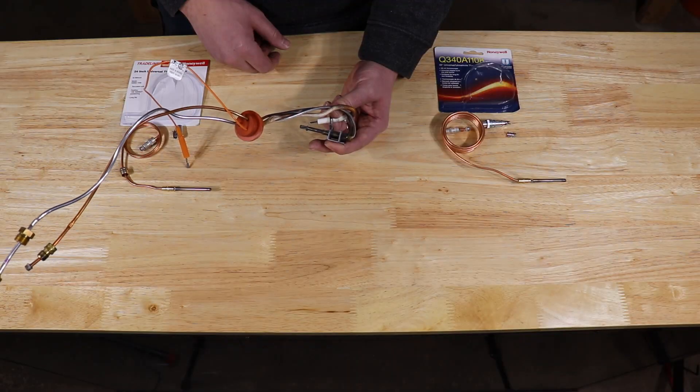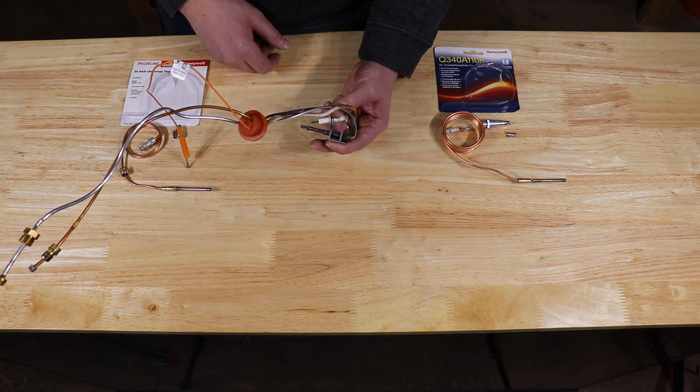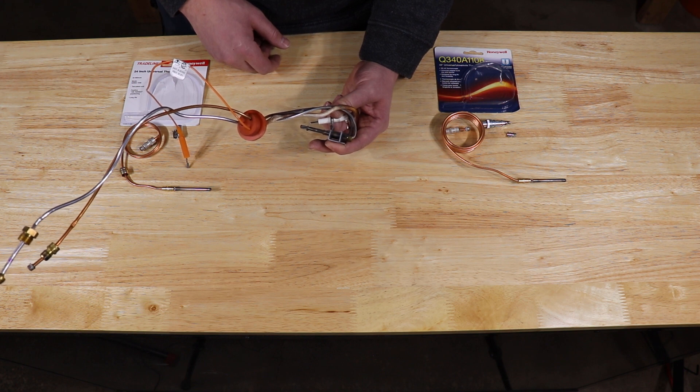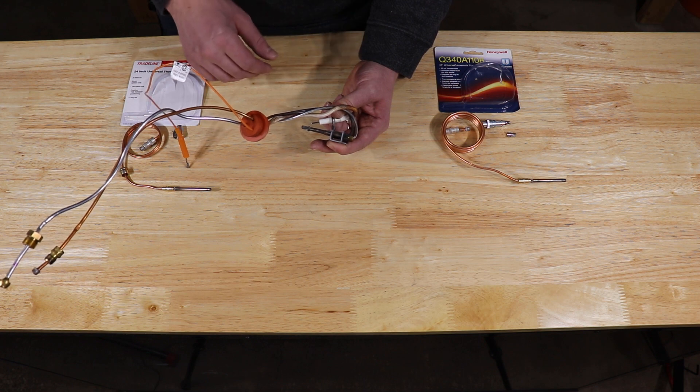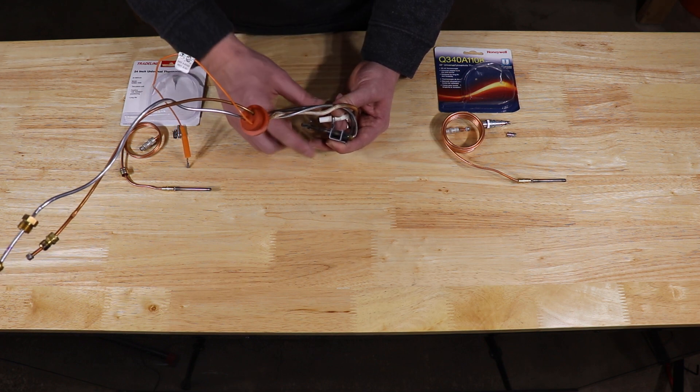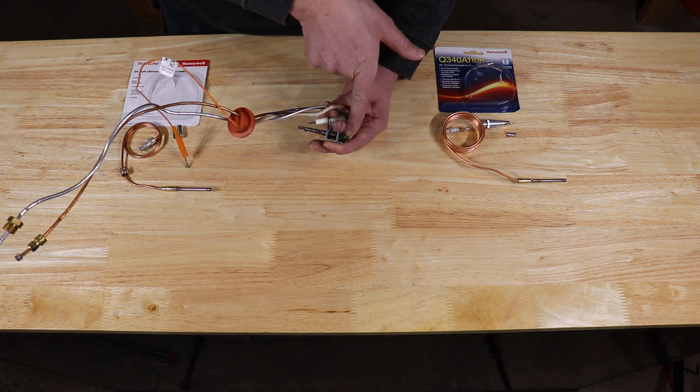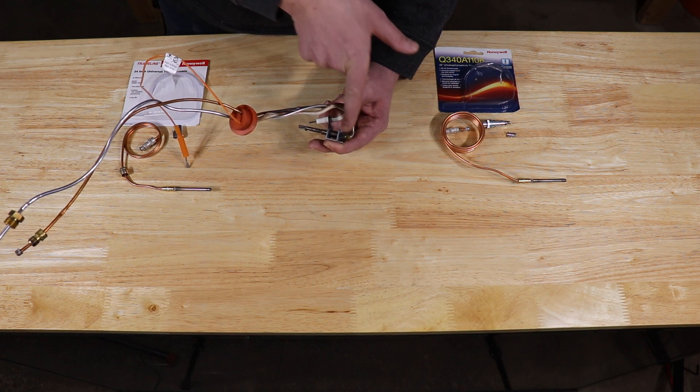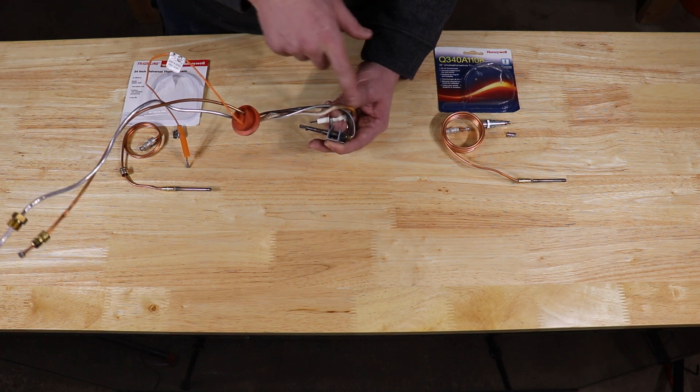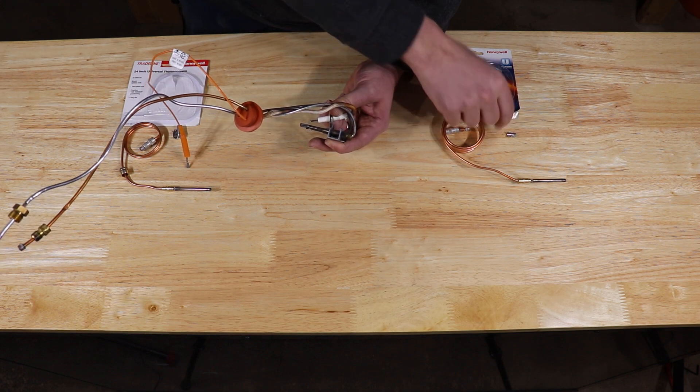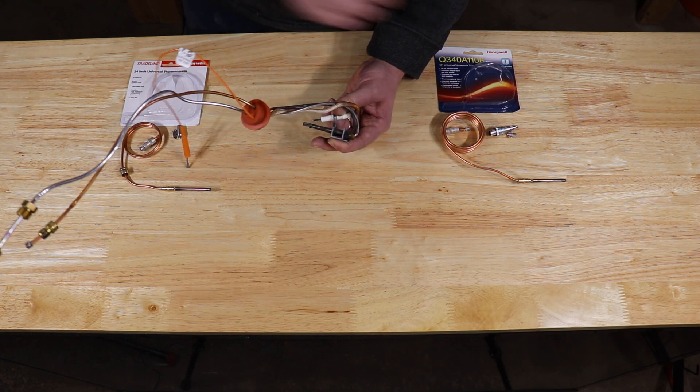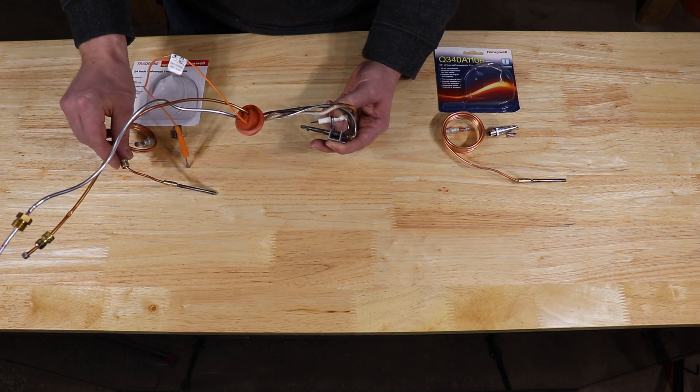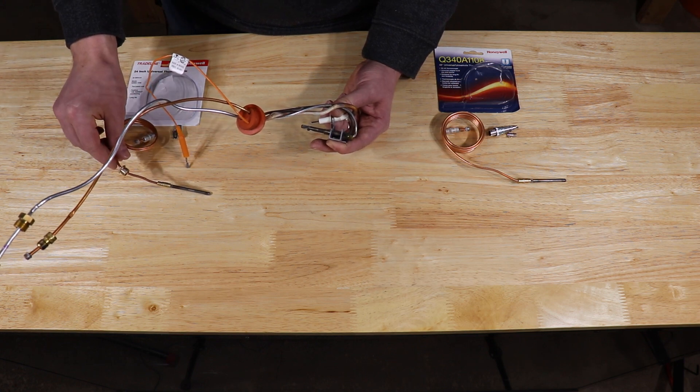Okay guys, now that you can change a push-fit style thermocouple, we'll go on to the screw-in style. I'm using this as demonstration purposes only as this is a push-fit style. The first hole here on this side would be threaded, the second hole would not, and it would either use your thermocouple adapter threaded one or the nut on the end of the thermocouple depending on the model that you purchased.